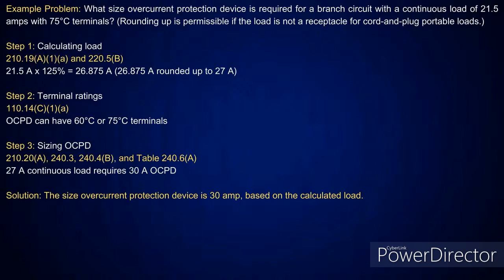Now, the only 2 places that doesn't hold true that I'm aware of at this point is phase converters. As we were looking at the other one where you size it at 250, you're going to have to go up because you have to protect the conductors. They're sizing that conductor that way. The other one is transformers, and transformers give you the option to go up or down because when you go down and pick up note 1, it says shall be permitted. That means you have the option to go up or down. Okay? Nice. And back probably 2 cycles ago, it didn't even say that. You just went down, and then if you were at 125% or less, you went up. Okay. But I'm going to show you why. Look at the tables and everything as we go through this and the wording, and you'll understand what I'm telling you is true here.